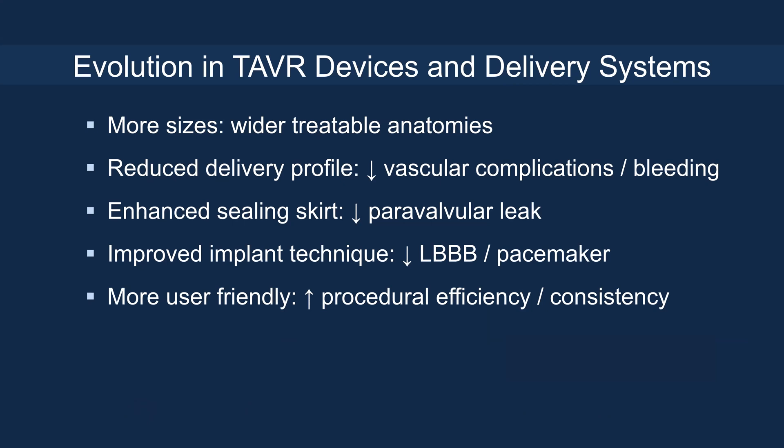Since then, there's been a significant evolution in TAVR devices and delivery systems. More sizes are available to treat wider anatomies. There's reduced delivery profile, meaning reduced vascular complications and bleeding. There's enhanced sealing skirt, meaning reduced paravalvular leak. There's improved implant technique, meaning left bundle branch block and pacemaker rate has gone down. And finally, the device is more user-friendly, increasing procedural efficiency and consistency.